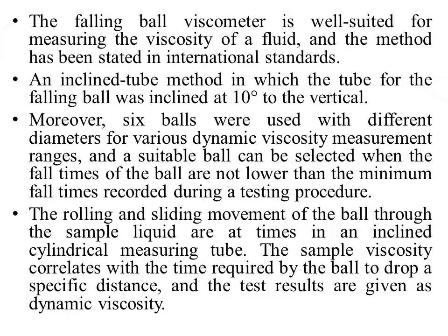It is well suited for measuring the viscosity of a liquid, and the method has been stated in international standards. They use 6 different balls with different diameters for various dynamic viscosity measurement ranges, and a suitable ball can be selected when the fall time of the ball is not lower than the minimum fall time recorded during the testing procedure. So you have to test many balls and then select a ball whose falling time is not lower than the minimum fall time.